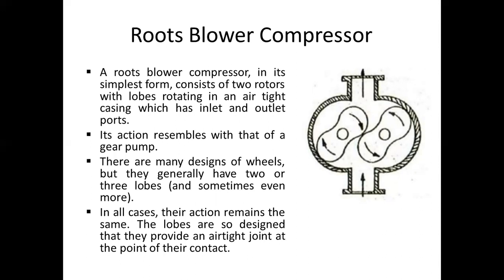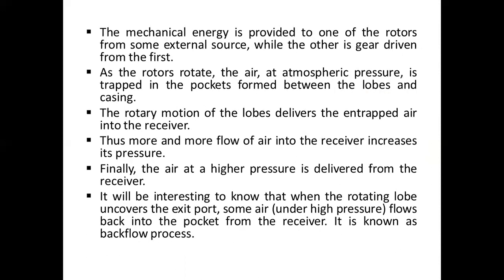In the Roots blower compressor, the mechanical energy is provided to one of the rotors from some external source, while the other is gear driven from the first. As the rotors rotate, the air at atmospheric pressure is trapped in the pockets formed between the lobes and casing.